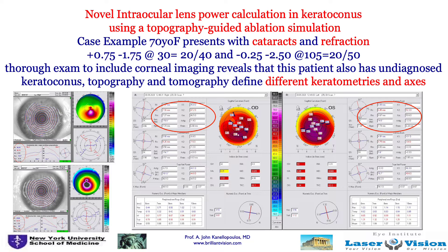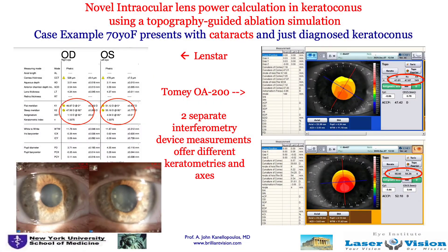The problem here is that each measurement we see differs. On the left, we're seeing the Placido reflection topographies with the Oculus device. On the right, we're seeing Pentacam images, which measure total cornea power — very important. We're also looking at the LENSTAR keratometry measurements, which measure a central circle to the vertex of 2.8 and 3.2 millimeters, and the Tomey OA-200 device, which is our second interferometer besides the IOLMaster. The difference between all these devices is that they give completely different keratometries in power and axis, because we're measuring an irregular cornea.